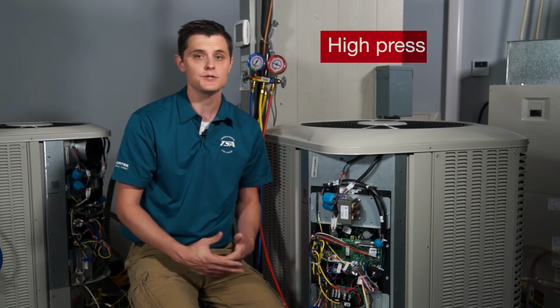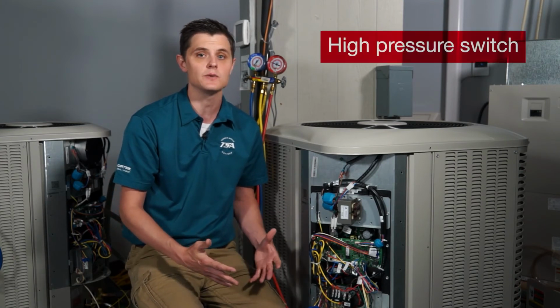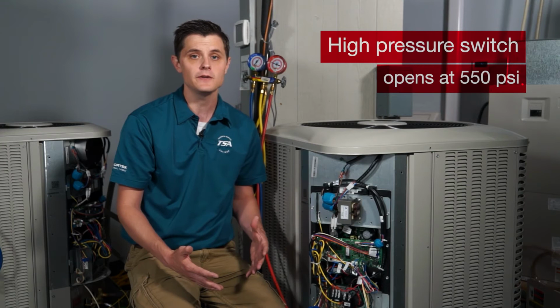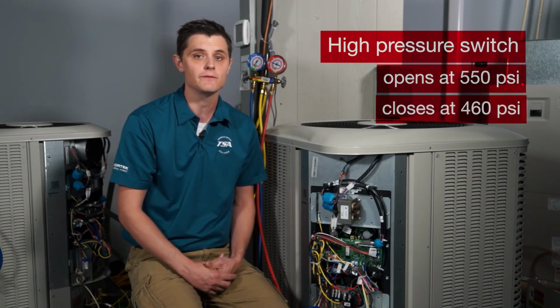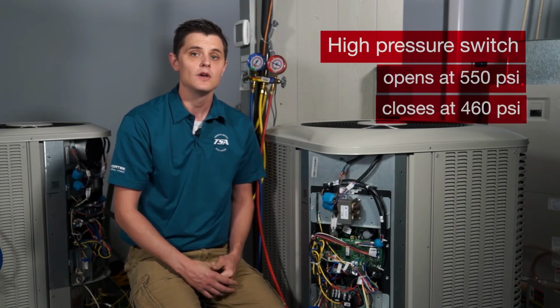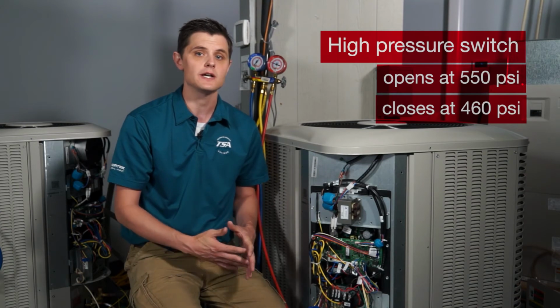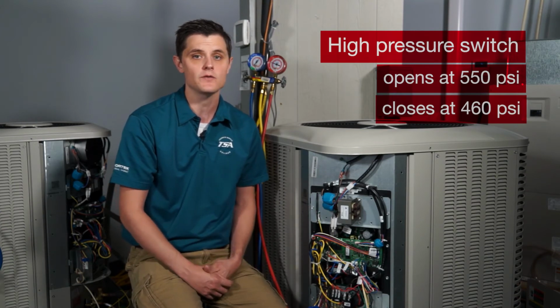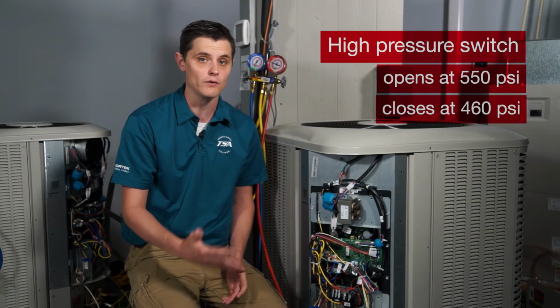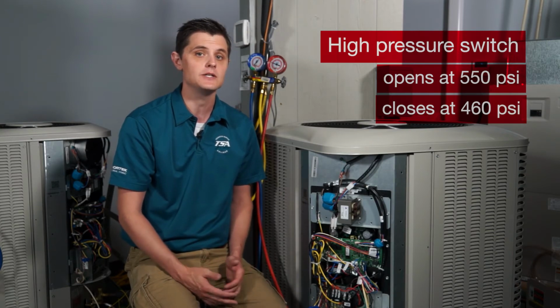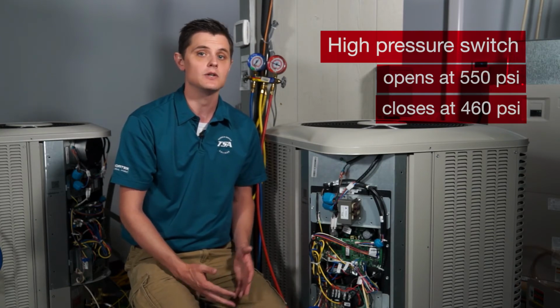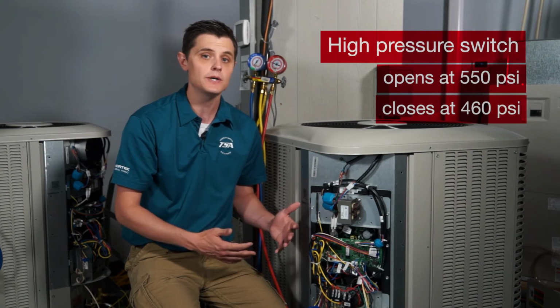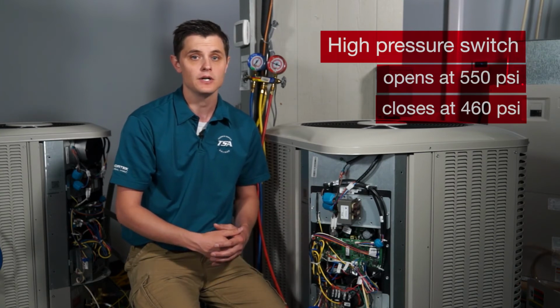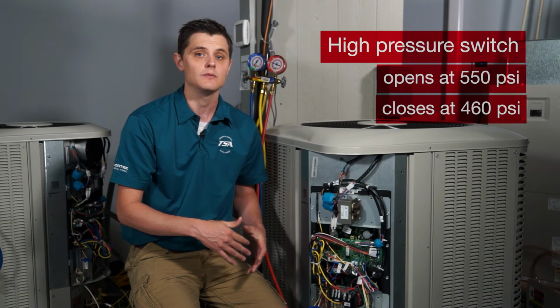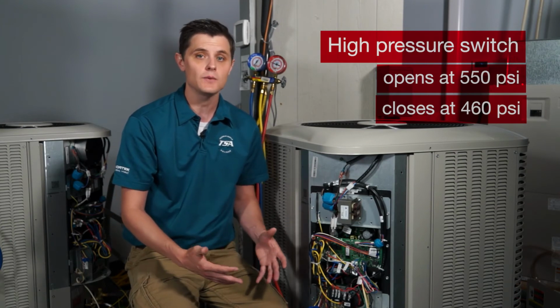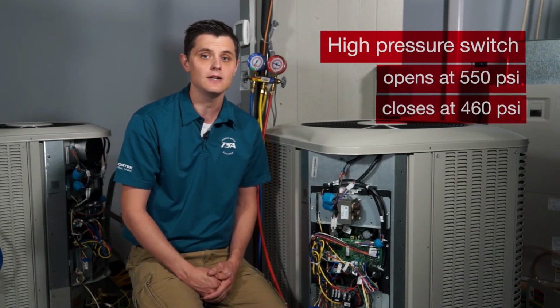Moving over to the high pressure switch side, the high pressure switch is going to open at 550 and then reclose at 460 PSI. When you're dealing with the high pressure switch side, most of the time what sets off a high pressure switch is either you're overcharged or you have a dirty condenser coil in cooling mode. Now, if you're in heat pump mode and you get a high pressure switch related problem, most of the time that's not enough airflow going across your indoor coil to get that heat off.